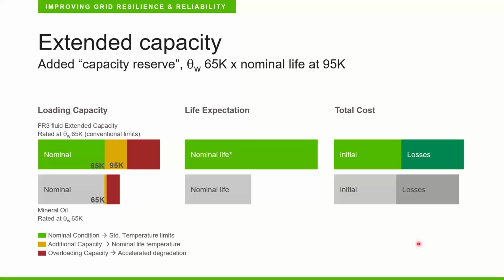And this matches what you said at the beginning, Stefan, about the peak curves on the demand that can be absorbed. It's not a continuous load of the transformer, it's temporary overloads. And also the increase in the temperature and the load that the harmonics are creating from the renewable energies. If we see this from the life expectation point of view, if the transformer is working at 65 degrees, we are at a very low loading of the transformer. So the nominal life can be increased between 1.5 and 2 times the nominal life of the transformer.